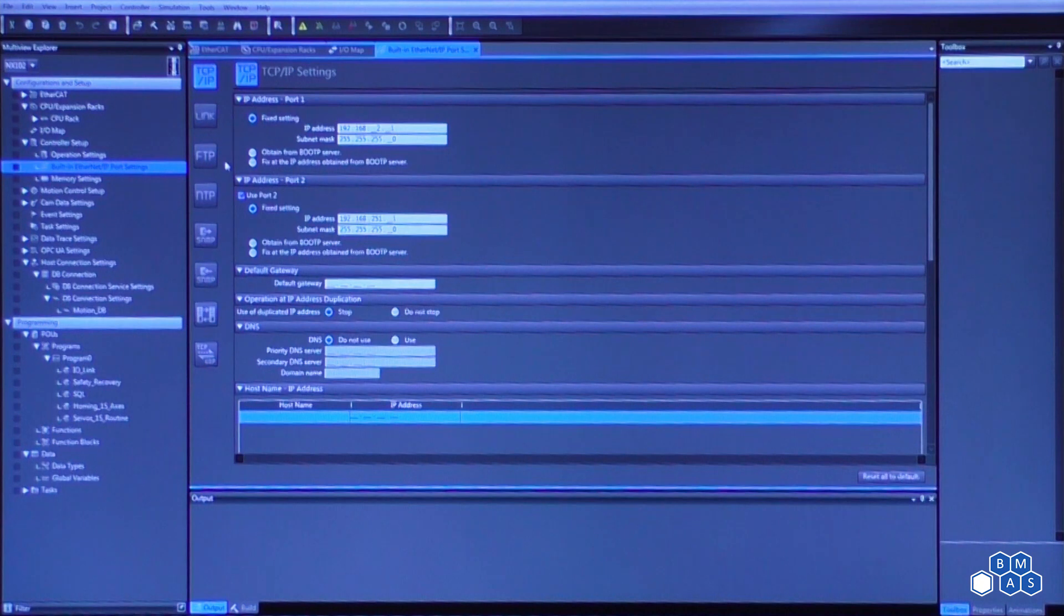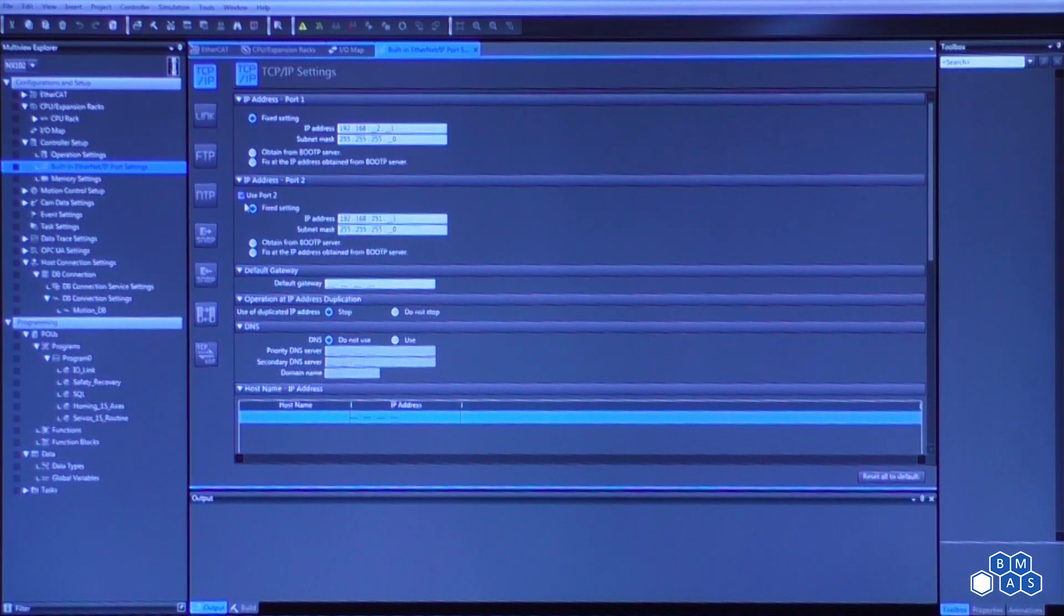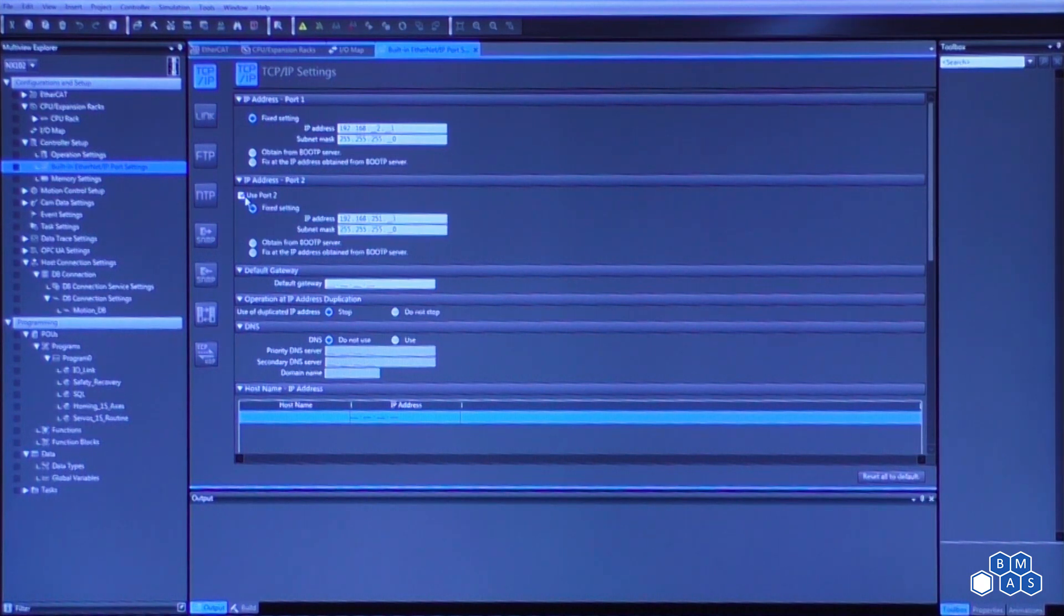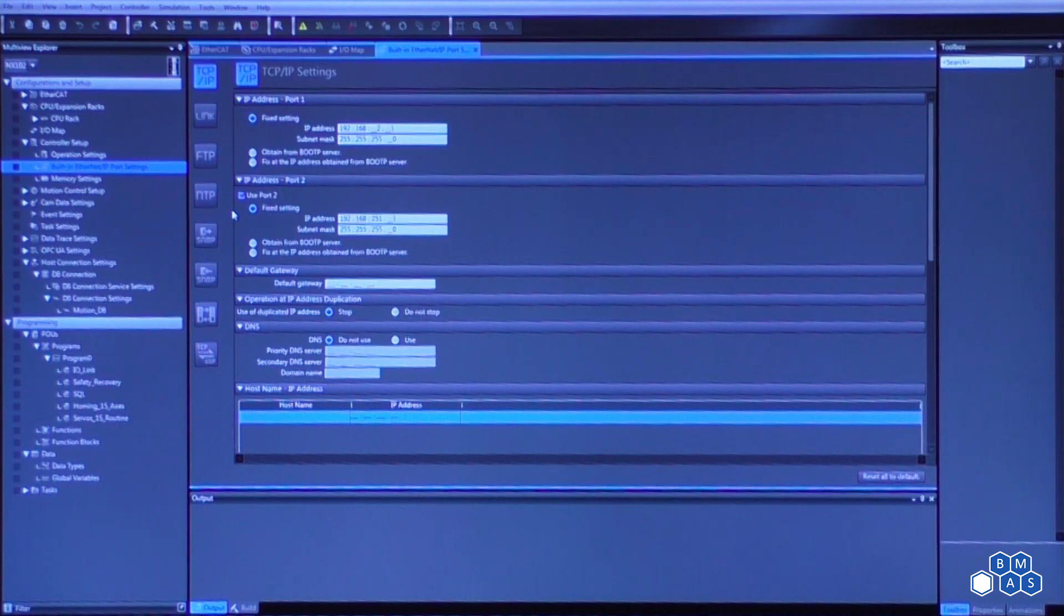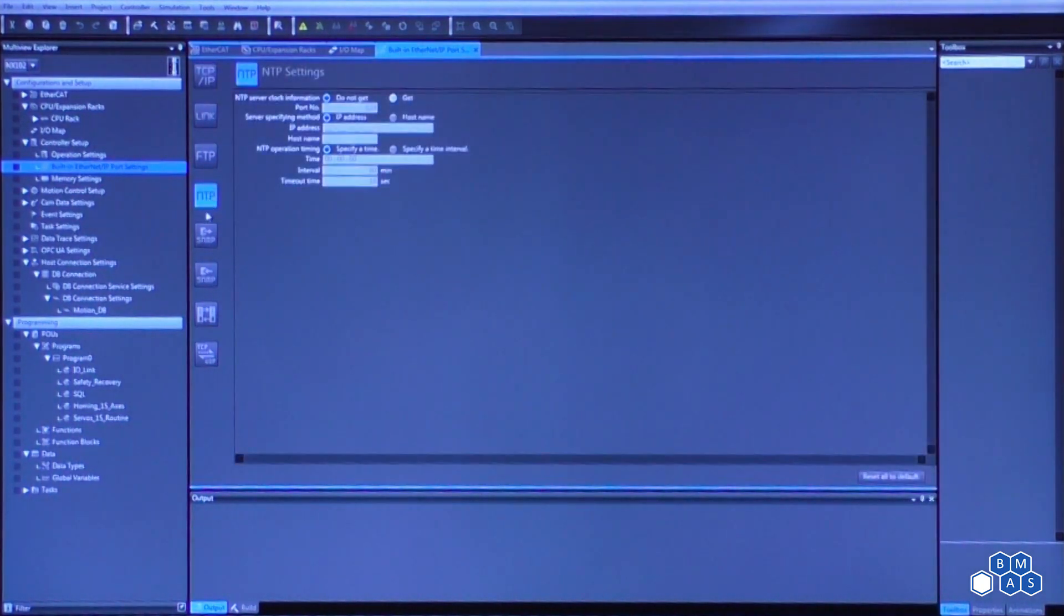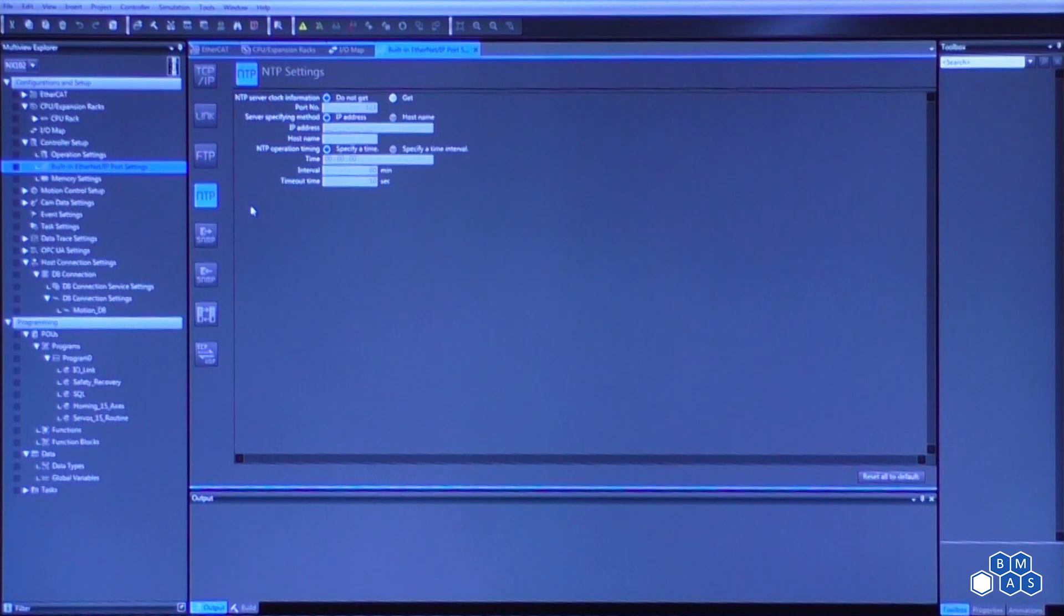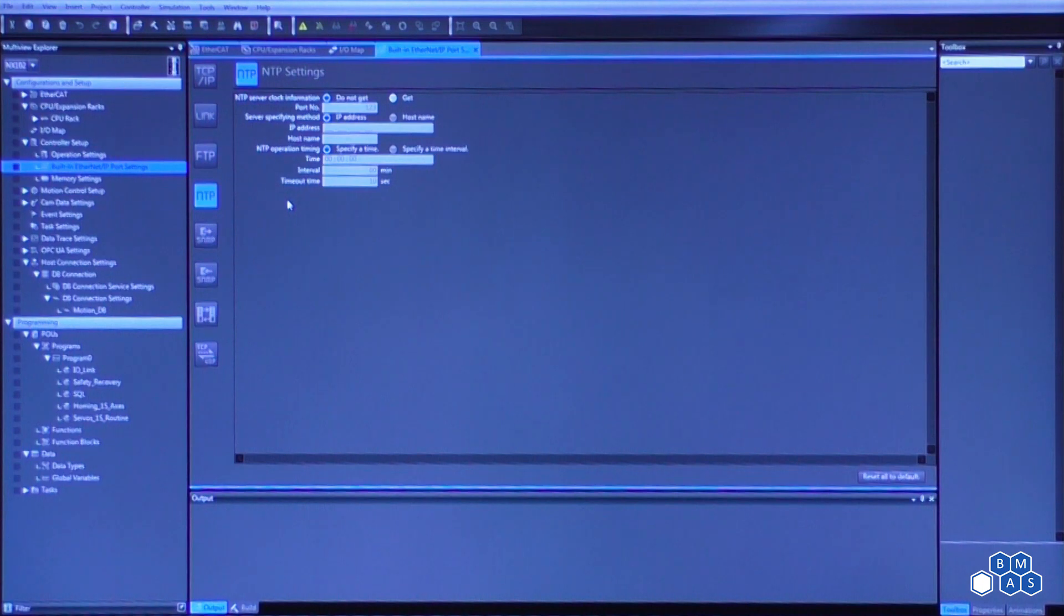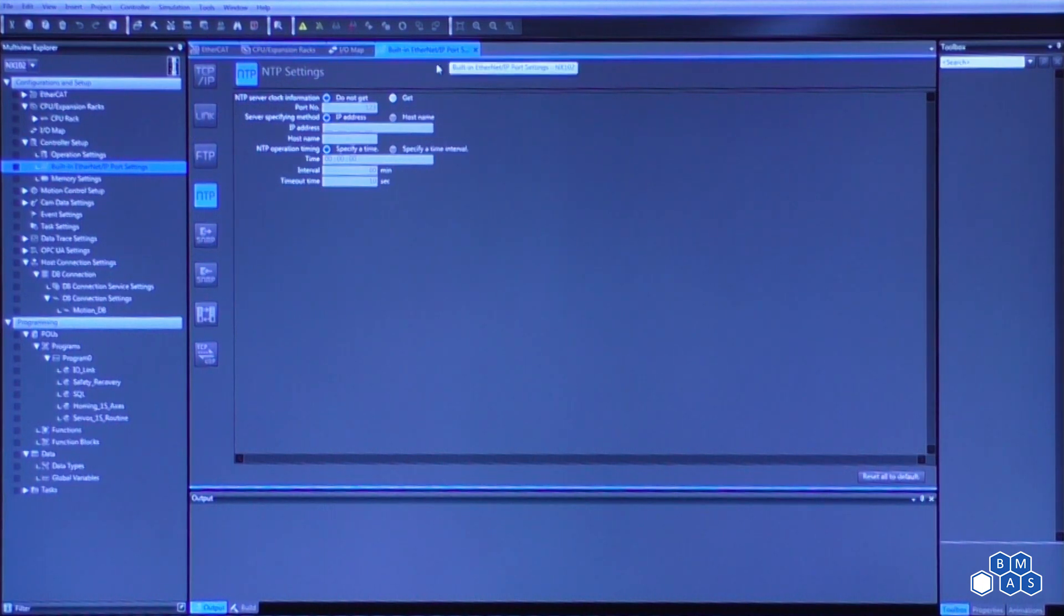You'll notice a lot of the other configuration options that are available with these ports. If I were to point out the one that is probably the most common when we're dealing with databasing or needing to capture productivity data or quality data, a lot of times it's a timestamp as to when that was captured. So what is very frequently done is we use a network time protocol that we would interface with a server that is maintaining the time, so we don't have to worry about the processor drifting over time, its time clock drifting. So I'd say that's what's very common.